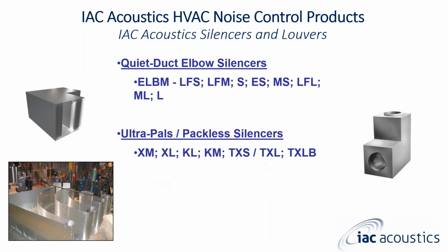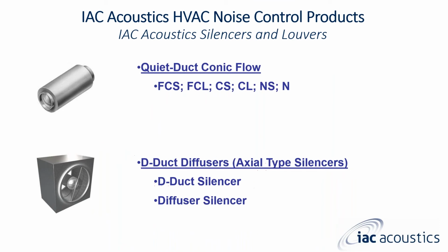We also have our TXS, TXL, and TXLB, which is the one to the right. These are our tubular packless silencers. These can range anywhere from 6 inches on up to 24 inches in diameter. We have our Quiet-Duct Conic Flow series, and then our D-duct diffusers. The D-duct diffusers are typically used with axial type fans, so these are axial type silencers. They are placed on the inlet and outlet of the axial fan.